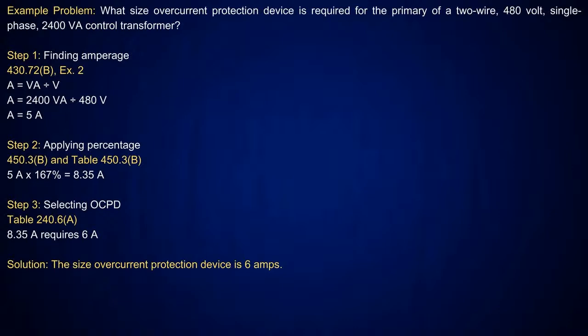Right. Now, this is very simple because when you go over there and look at that, I'm just doing the primary only here because we're talking about required for a primary 2-wire transformer here. And you go over and you look at currents less than 9 amperes. You come in and then you look at the next column. It says currents less than 2 amperes. So I'm between 2 and 9 amperes, right? So if I come down and I'm doing primary only, it tells me take it at 167%.